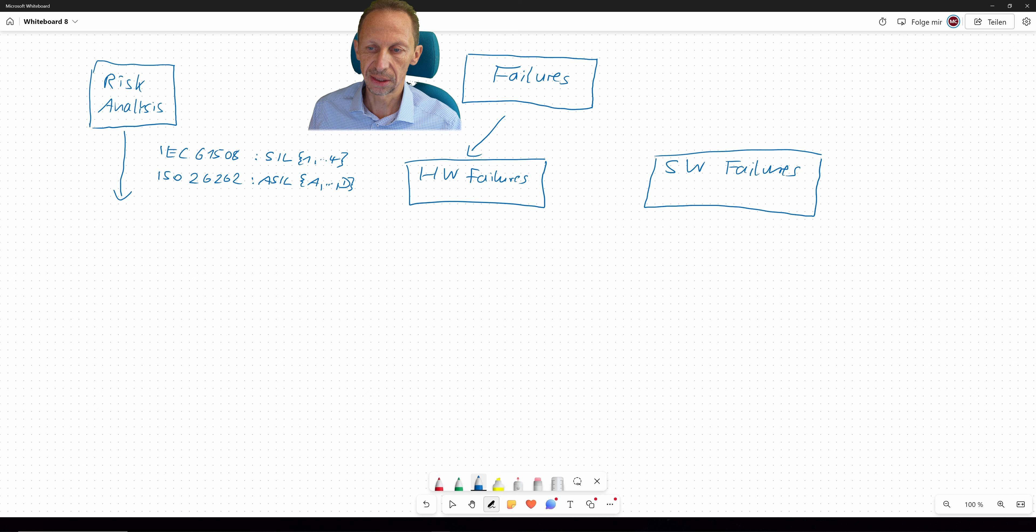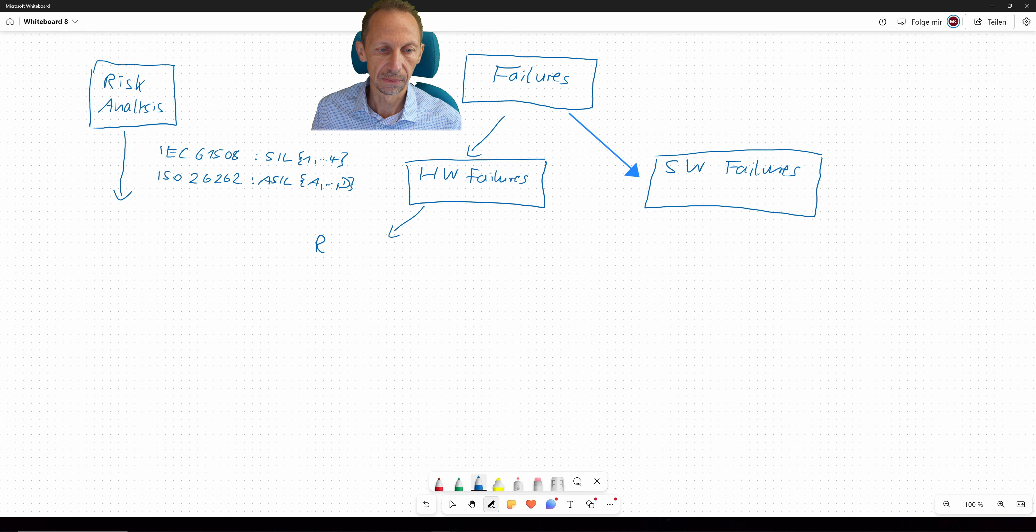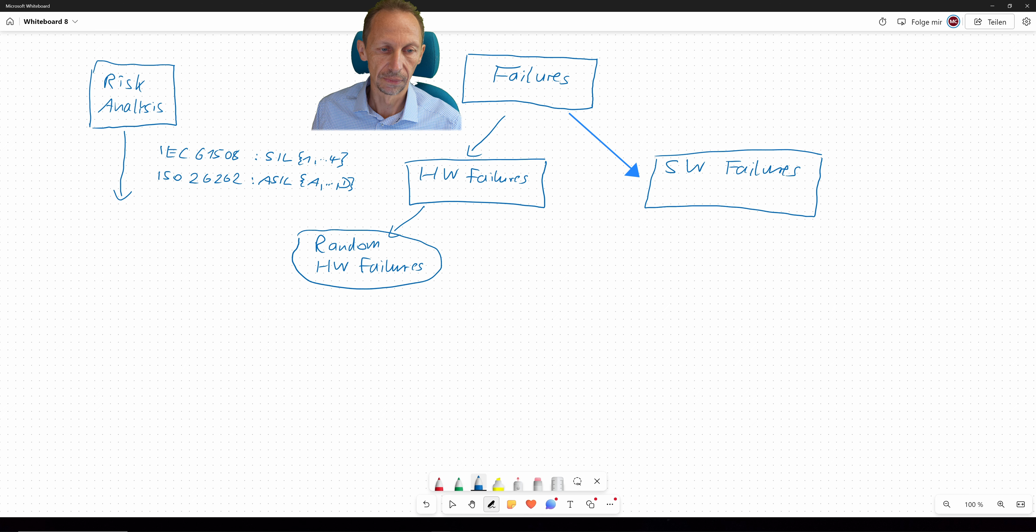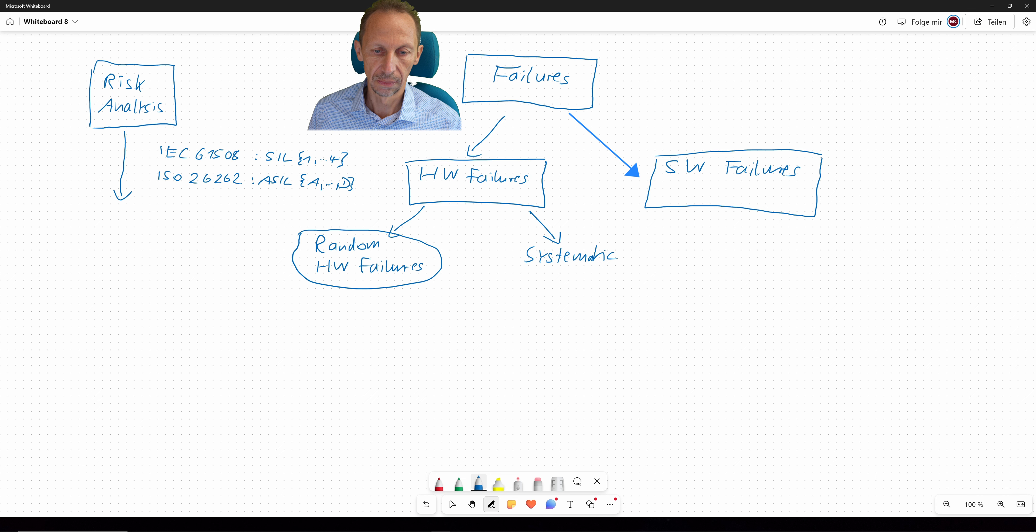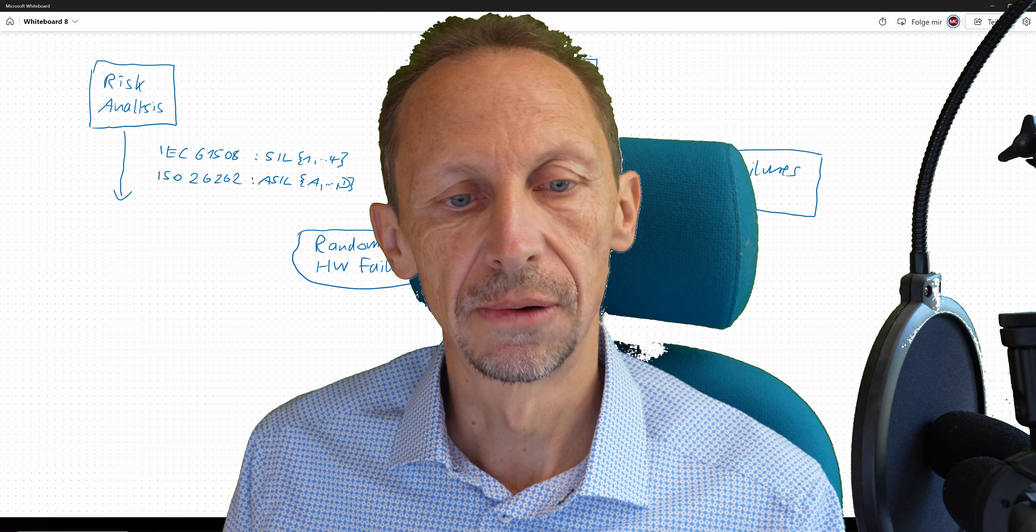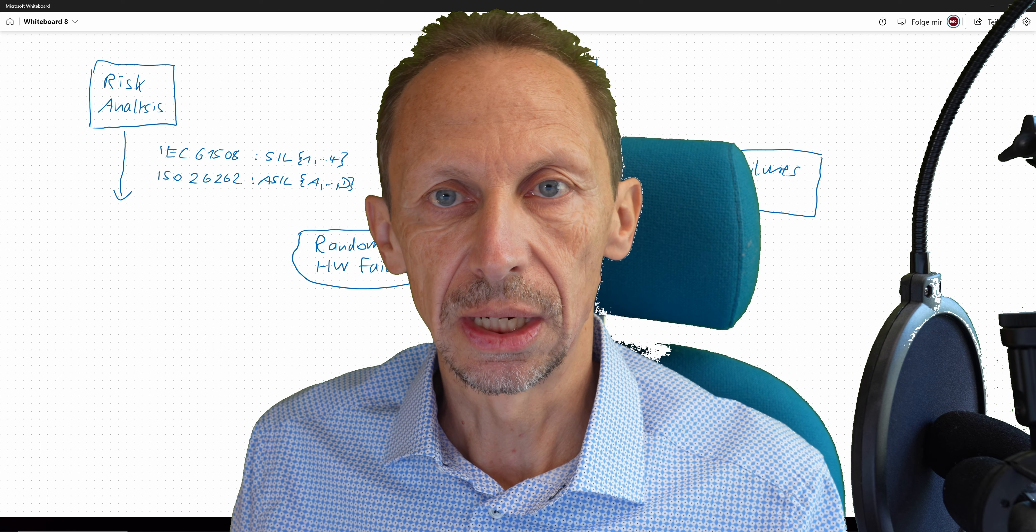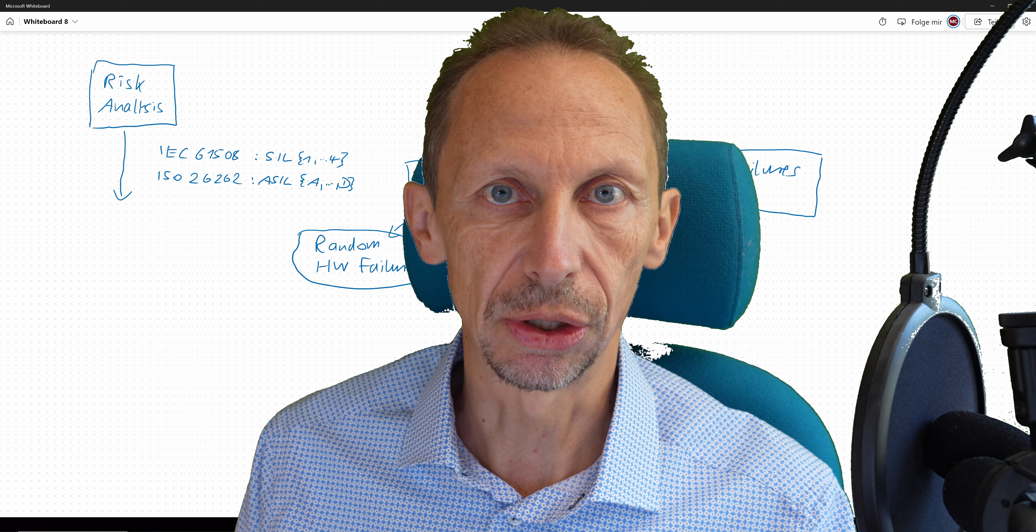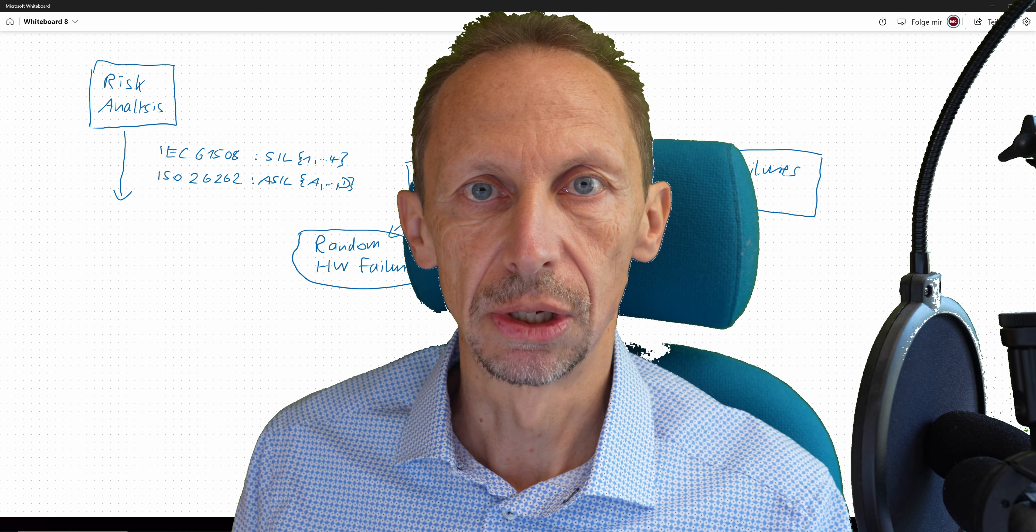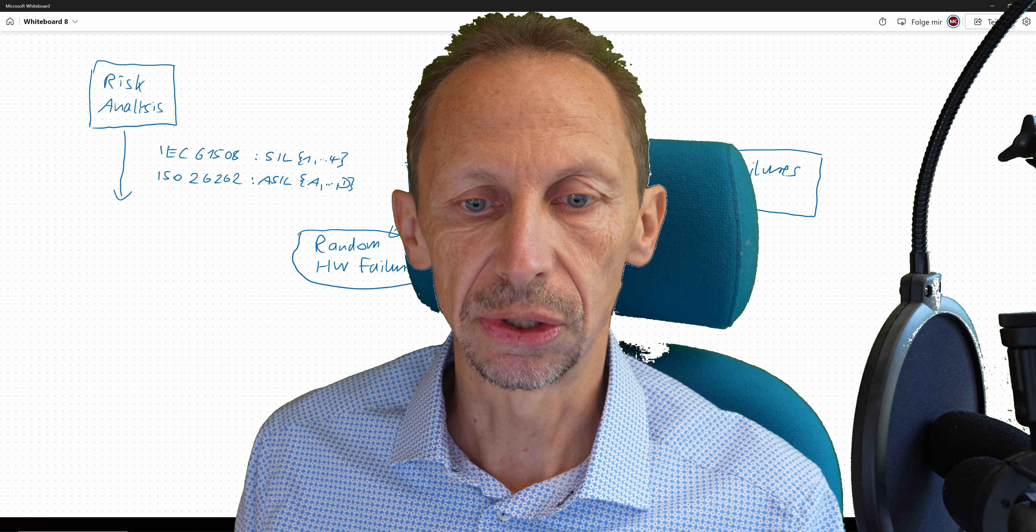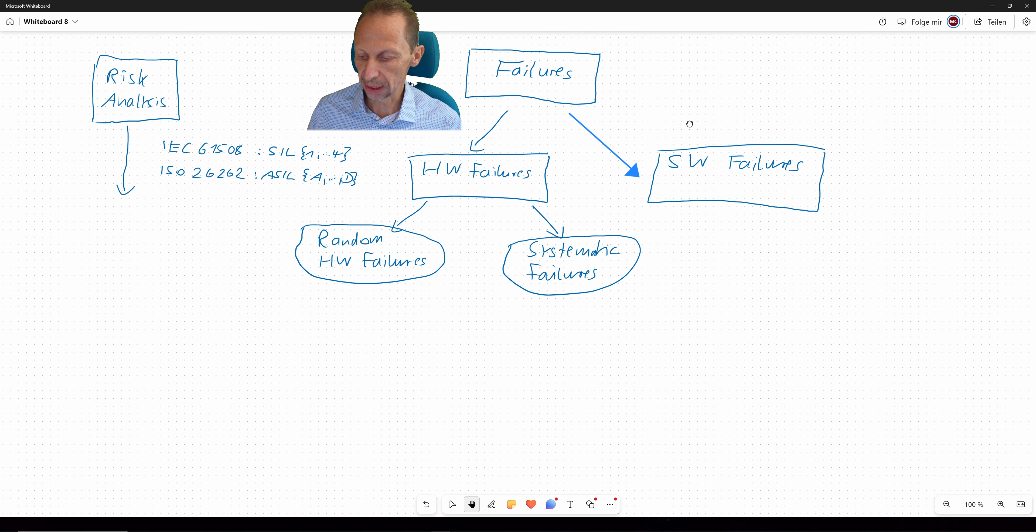Let's stick in the first step on the hardware failures. There will be another categorization into so-called random hardware failures and systematic failures. What is the difference here? Random hardware failures are about a part that suddenly has a defect due to aging. For example, a transistor burns. While systematic failures are due to bugs or mistakes being done during the development. So this is quite a different way of regarding failures.